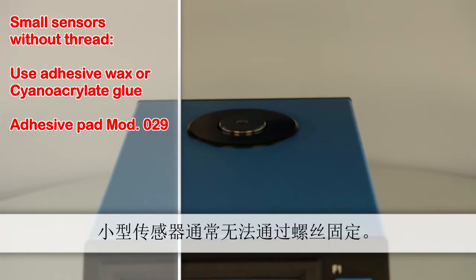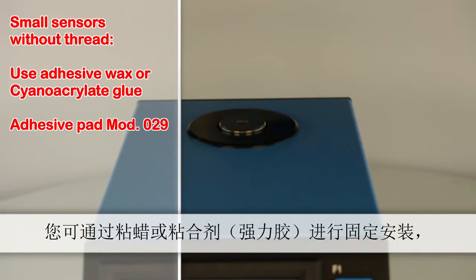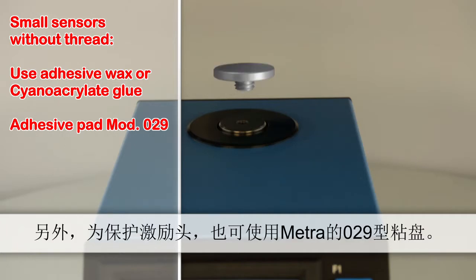Small sensors often don't have a mounting thread. In this case you can use adhesive wax or cyanoacrylate. Alternatively, to safeguard the shaker head, use a Metra Type 29 adhesive pad.